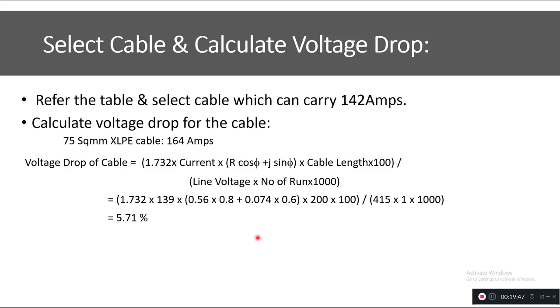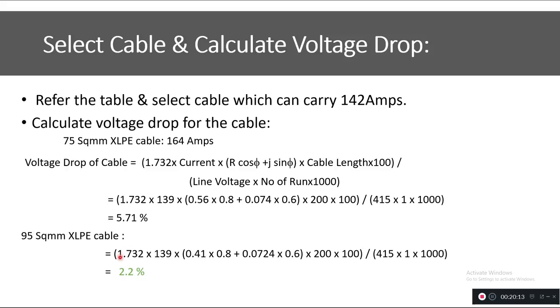At this point, you can either increase the number of cable runs — using two cables instead of one to halve the voltage drop — but in our case the current is not high enough to justify a second run. So instead, we increase the cable size from 70 mm² to 95 mm². Recalculating the voltage drop for 95 mm² using the resistance and reactance from the datasheet gives 2.2%, which satisfies our voltage drop criterion.